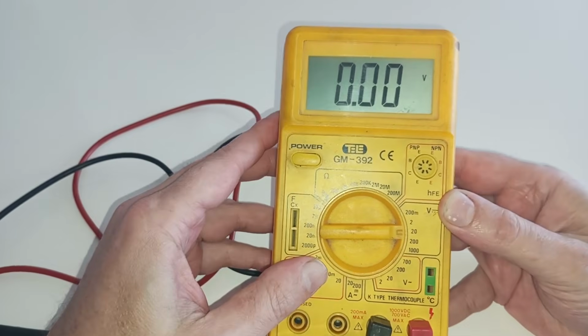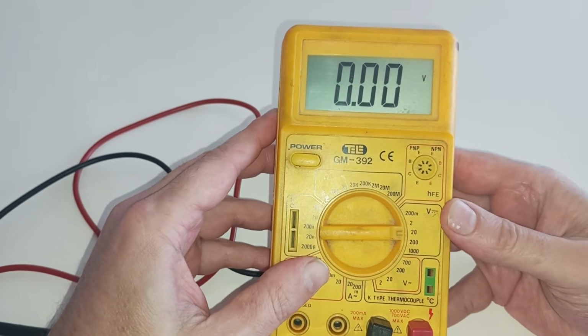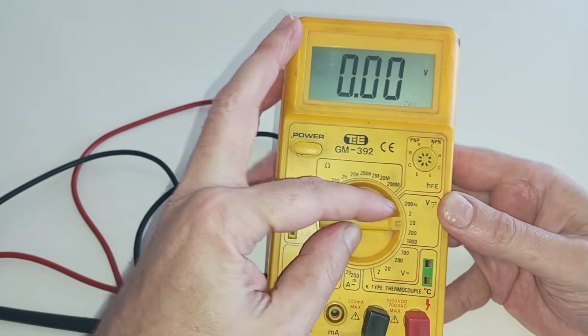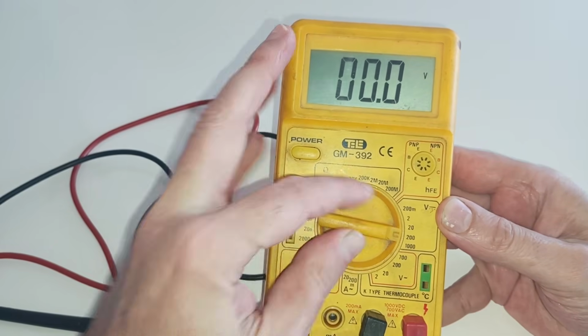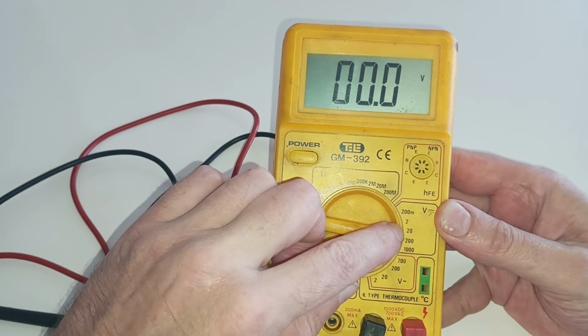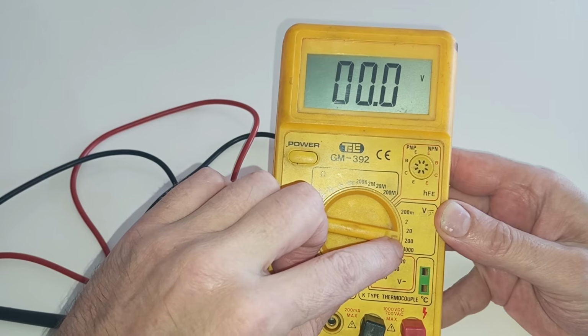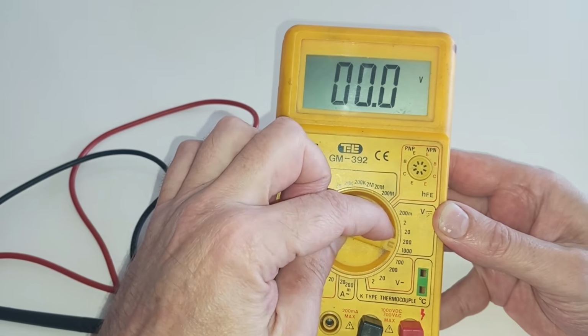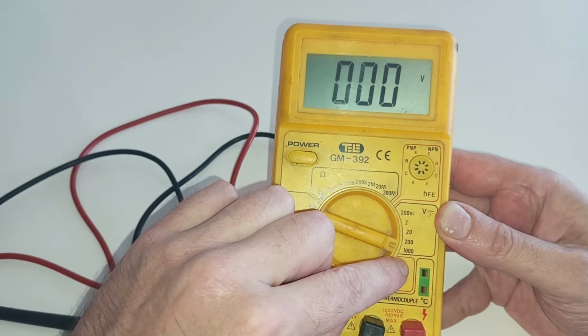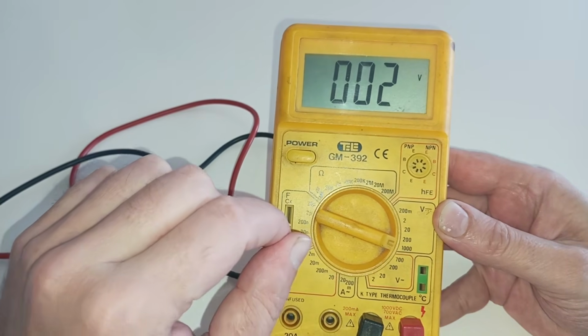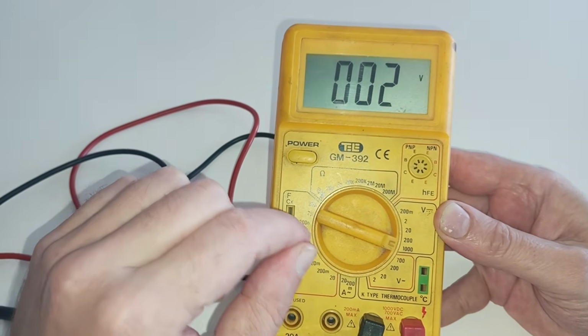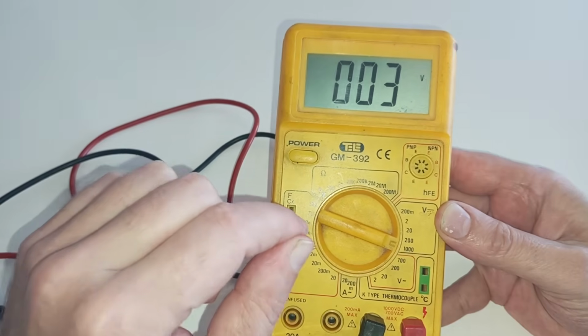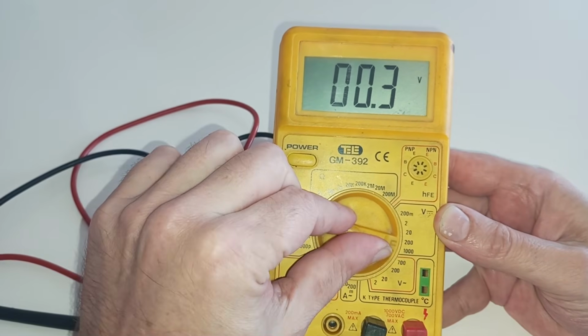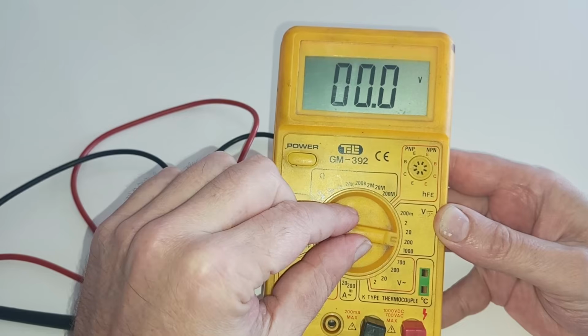If you want to measure a direct current voltage of 150 volts, you set it to 200, because 150 is more than 20 but less than 200. If you want to measure 500 volts, set it to 1000, since that's higher than 500. It's always good to know the nominal value of what you're measuring, then set the instrument accordingly.